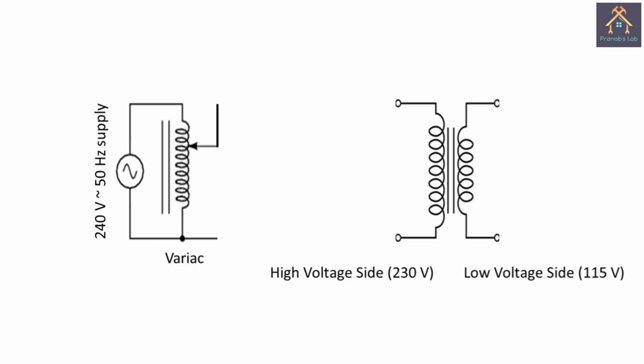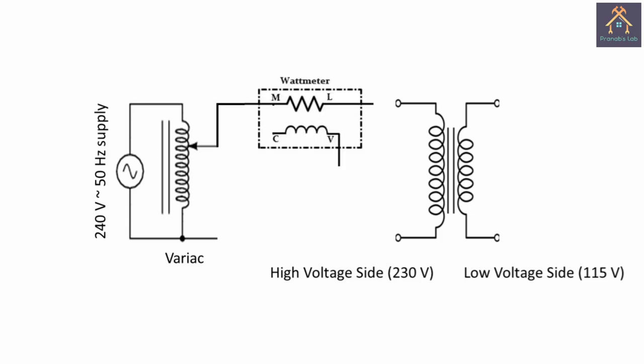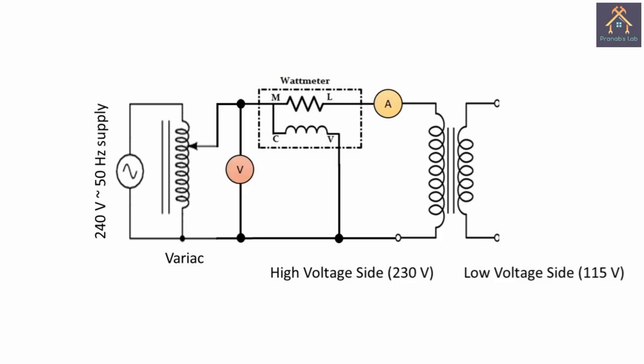A single phase 240 volt supply is connected with a single phase variac. From the variac, it is connected with the M terminal of the wattmeter. The M and C terminals of the wattmeter are shorted. The L terminal of the wattmeter is connected with an ammeter. From the ammeter, it is connected with the high voltage side, and from the high voltage side it is connected back to the variac. The V terminal of the wattmeter is connected with the common terminal of the variac. A voltmeter is connected across the high voltage side of the transformer.